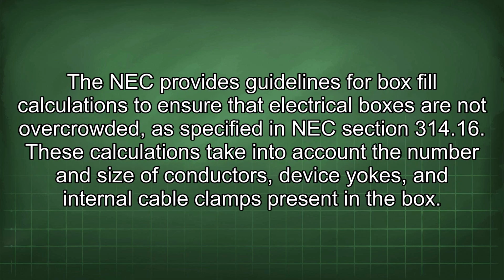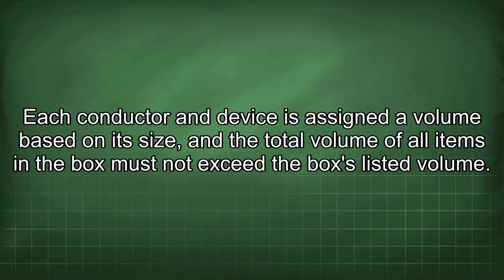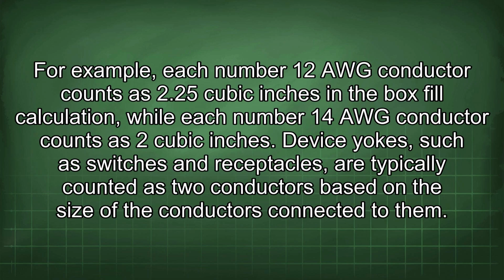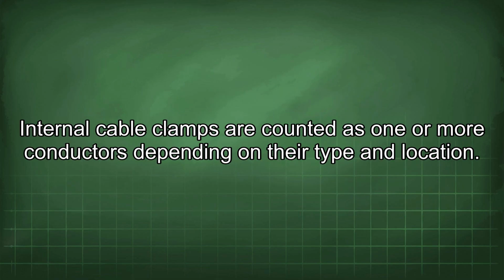The NEC provides guidelines for box fill calculations to ensure that electrical boxes are not overcrowded, as specified in NEC section 314.16. These calculations take into account the number and size of conductors, device yokes, and internal cable clamps present in the box. Each conductor and device is assigned a volume based on its size, and the total volume of all items in the box must not exceed the box's listed volume. For example, each number 12 AWG conductor counts as 2.25 cubic inches in the box fill calculation, while each number 14 AWG conductor counts as 2 cubic inches. Device yokes such as switches and receptacles are typically counted as 2 conductors based on the size of the conductors connected to them. Internal cable clamps are counted as 1 or more conductors depending on their type and location.